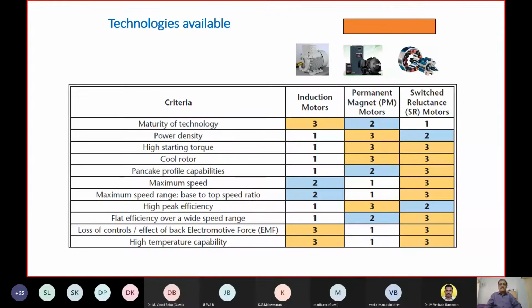So I will just briefly touch upon the 3 technologies available for motor manufacturing. What is familiar to us with over 130 years of existence is the induction motor. Fairly new are the 2 other technologies, which are permanent magnet, PM motors, and switched reluctance motors. These 2 motors are synchronous motors, while the induction motor is an asynchronous motor. So while we talk about replacing the induction motor for higher efficiency potential through permanent magnet motors or switched reluctance motors, in other words, PMSM and SRSM, this is how motors are referred to in the market. So these 2 can comfortably meet IE4 or even IE5 whenever it is adopted, while induction motors will have limitations in going beyond IE4 efficiencies.